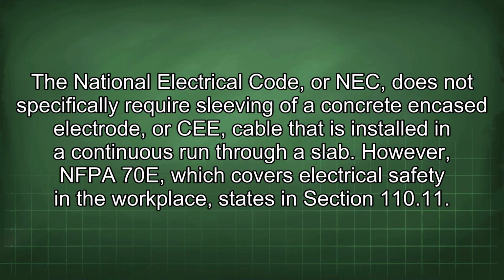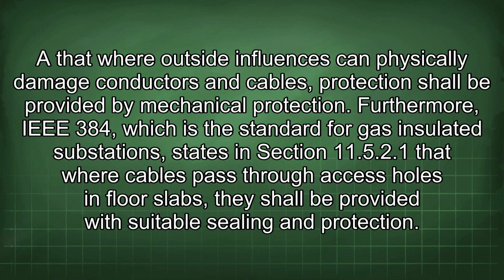The National Electrical Code, or NEC, does not specifically require sleeving of a concrete encased electrode, or CEE, cable that is installed in a continuous run through a slab. However, NFPA 70E, which covers electrical safety in the workplace, states in section 110.11 that where outside influences can physically damage conductors and cables, protection shall be provided by mechanical protection.